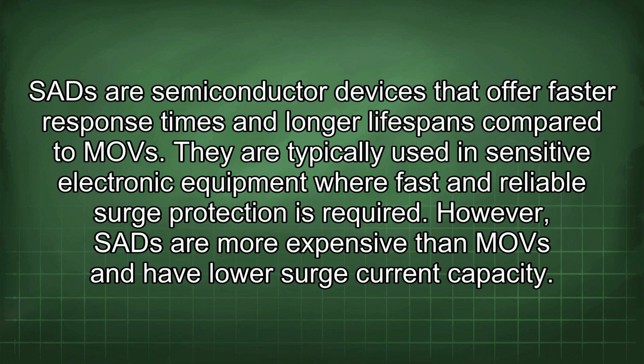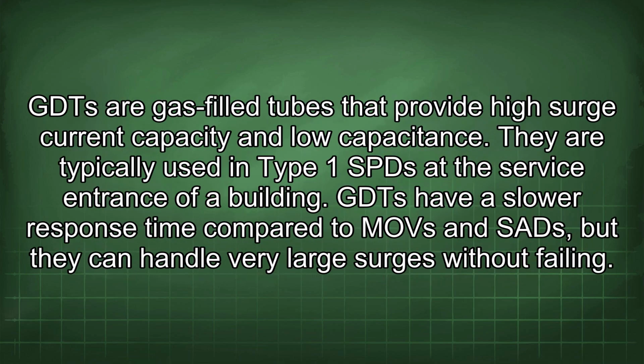SADs are semiconductor devices that offer faster response times and longer lifespans compared to MOVs. They are typically used in sensitive electronic equipment where fast and reliable surge protection is required. However, SADs are more expensive than MOVs and have lower surge current capacity. GDTs are gas-filled tubes that provide high surge current capacity and low capacitance. They are typically used in Type 1 SPDs at the service entrance of a building. GDTs have a slower response time compared to MOVs and SADs, but they can handle very large surges without failing.